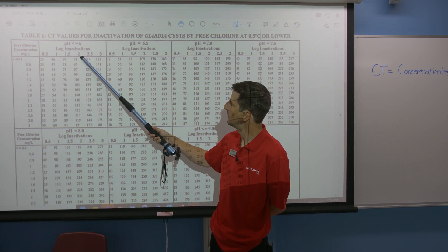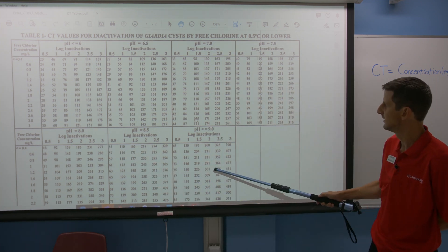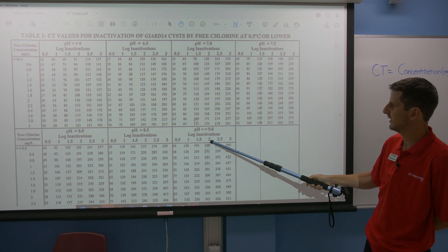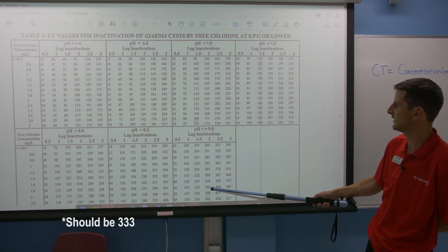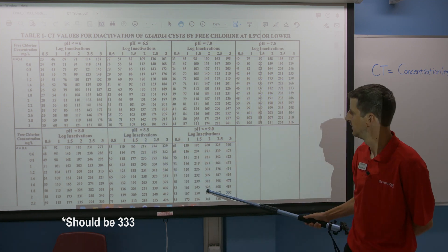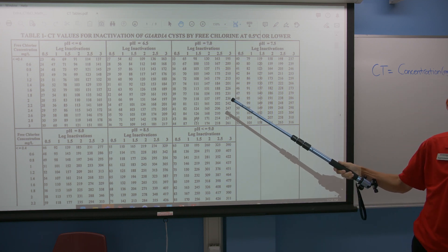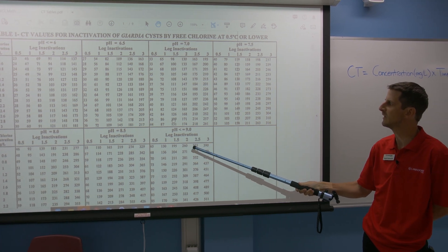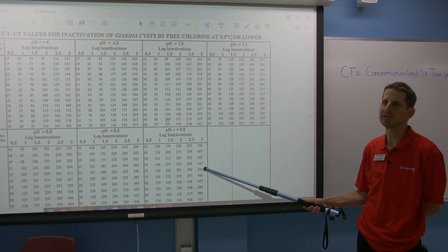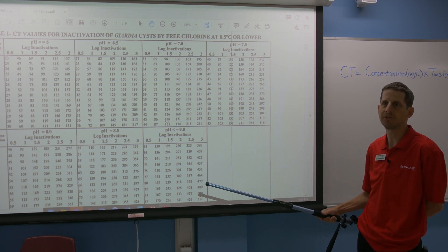Now let's look at 2-log removal at 2 mg/L concentration but at pH 9 — we get 326. So 326 compared to 110: this number is three times higher, meaning you need much more CT to achieve the same inactivation. So disinfection at a lower pH is much better — you want your water to be more acidic for disinfection by chlorine. And of course you can control your pH by using different additives to your water.